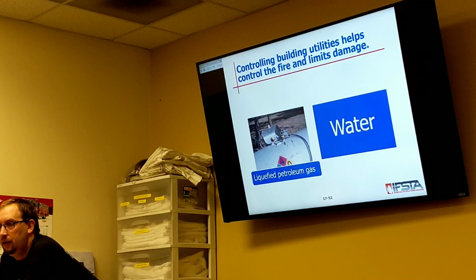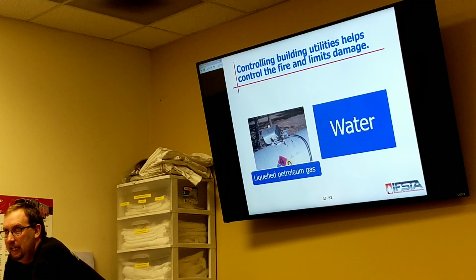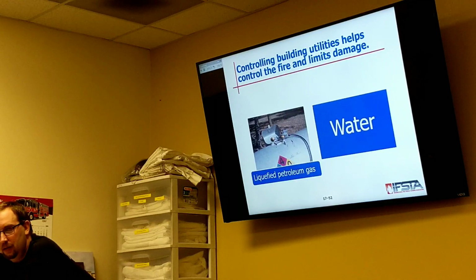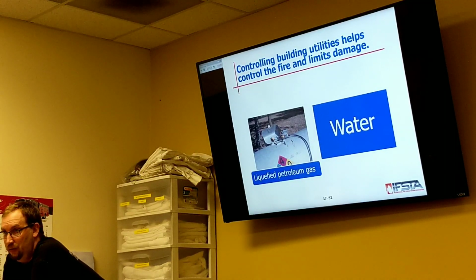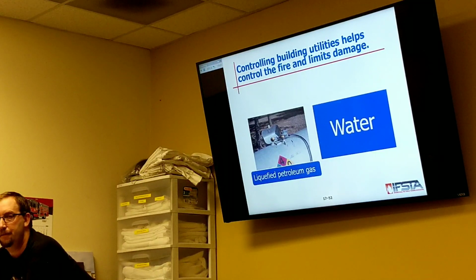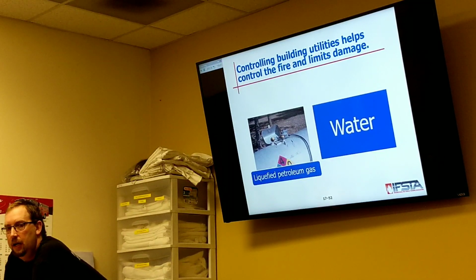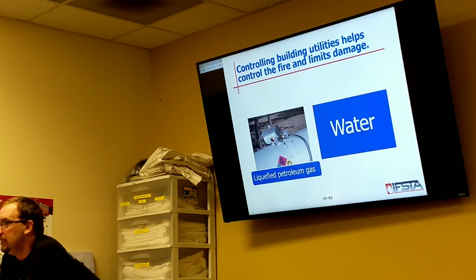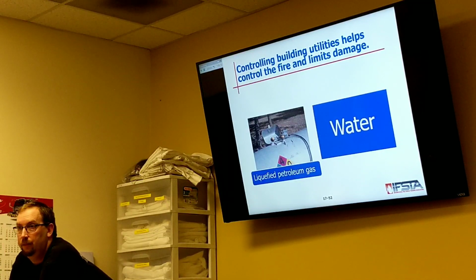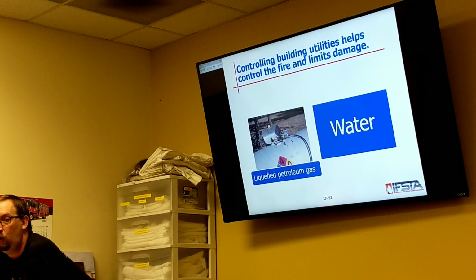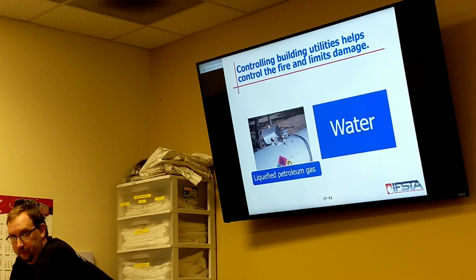If you have fire impingement on an LP tank, get that gun and just deluge it. You have to flow, I believe it's 500 gallons a minute for every point of impingement, and the point of impingement is the size of a football on an LP tank, to keep it cool enough to not explode.